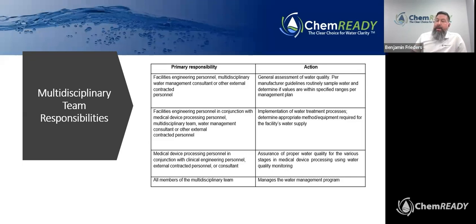The city water supply can vary vastly in being compliant with the utility water standards. Also included are medical device processing personnel in conjunction with clinical engineering or external consultants. Their actions and responsibilities include assurance of proper water quality for the various stages in the medical device processing, and they do that through water quality monitoring. And then all members manage the entire water management program to make sure that from the entrance of the city water into your facility all the way to the final sterilization step in your process, everybody is responsible to make sure that the program as a whole is compliant.